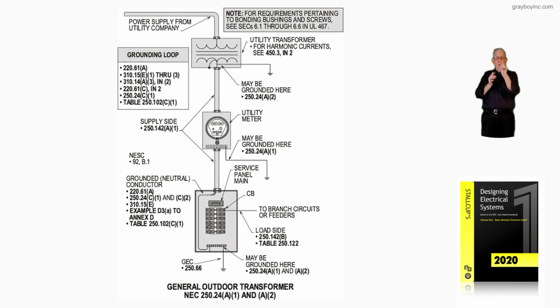The supply side is 250.142(A)(1). Now on the load side, you'll see the circuit breaker and the panelboard with the equipment ground and branch circuits going out, and then load side grounding is discussed in 250.142(B). But the equipment ground is sized based upon the breaker. You'd say, well, I have a 30 amp breaker. Then table 250.122, with your experience, you know this automatically, it'd be a number 10. Remember now, small conductors in 240.4(D) as in dog are number 10 down to number 18. Anything over number 6, like number 4 and larger, is considered large conductors and sets the pace and the fundamental requirements for sizing other boxes and things that deal with such size conductors.